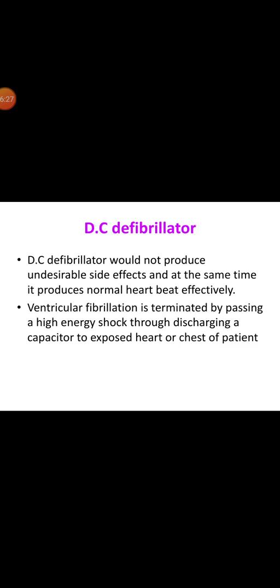the amount of electrical energy discharged by the capacitor may range between 100 and 400 watt-seconds, or joules. The duration of the effective portion of the discharge is approximately 5 milliseconds, and the energy delivered is represented by the typical waveform, which I can show in the following slides. As you can see, the peak value of the current is nearly 20 amps and that wave is essentially monophasic, since most of its excursion is above the baseline.